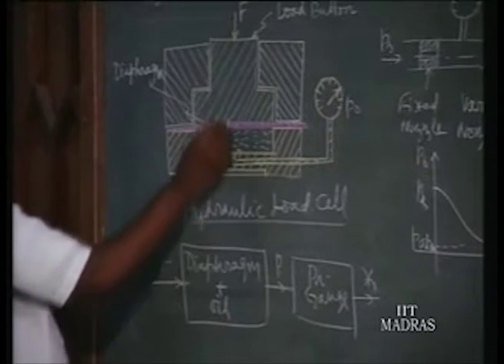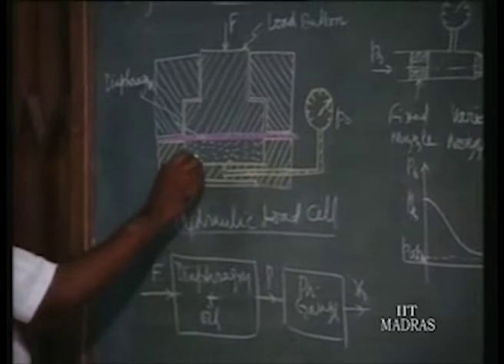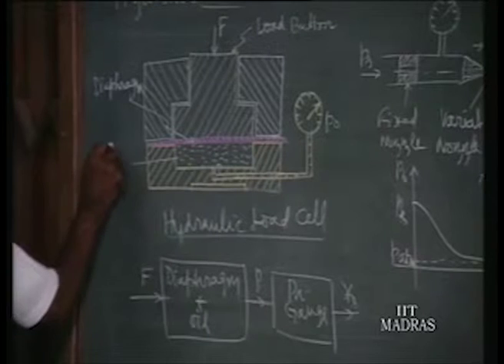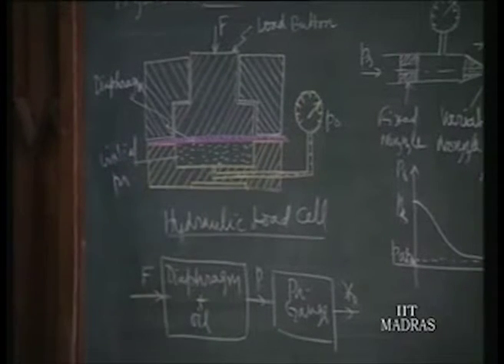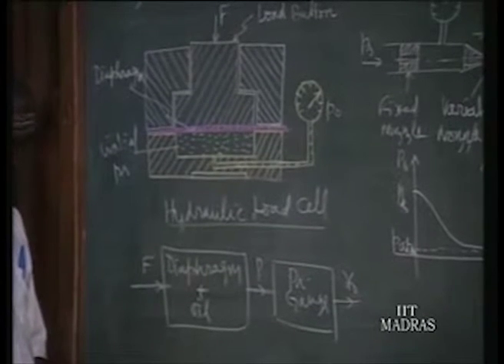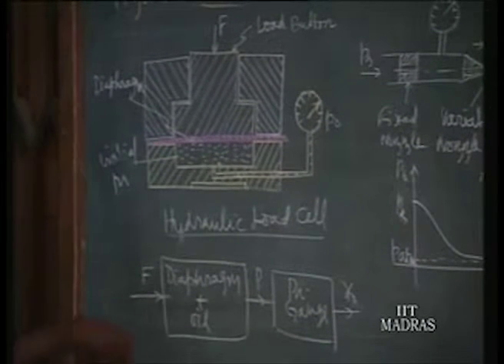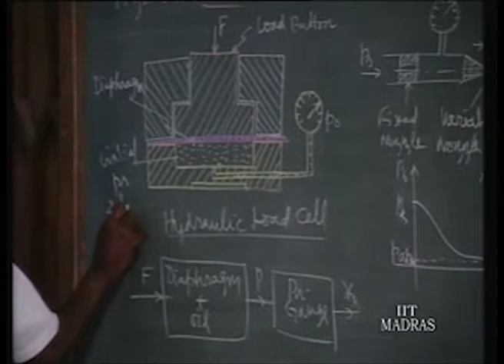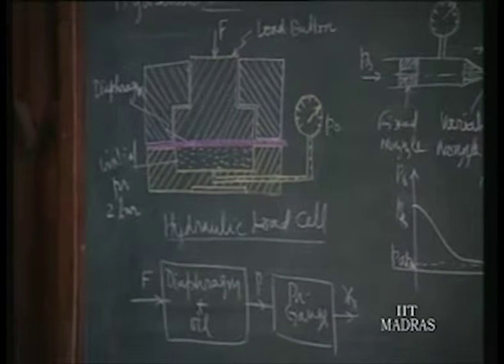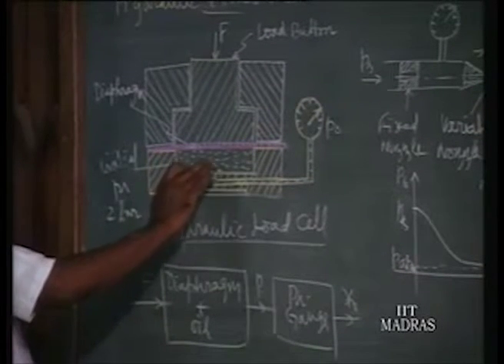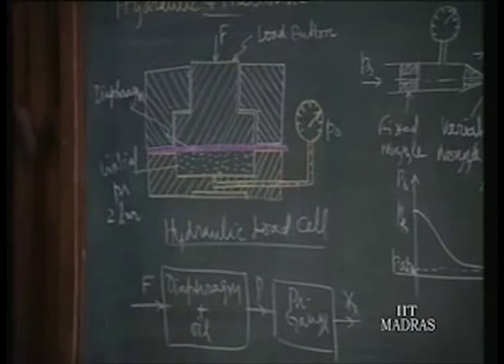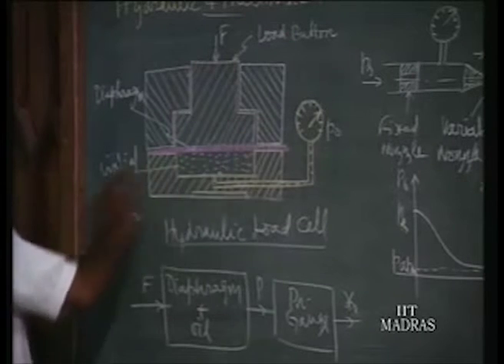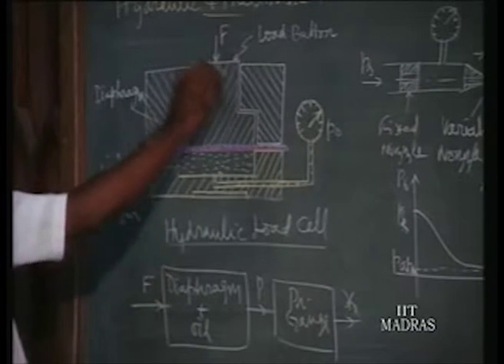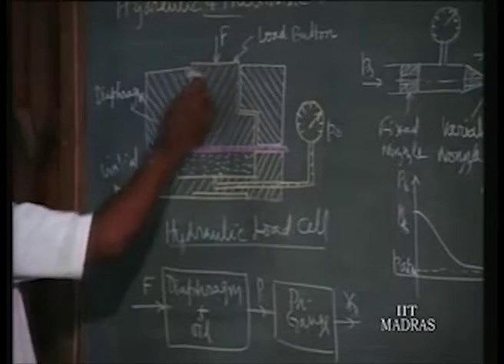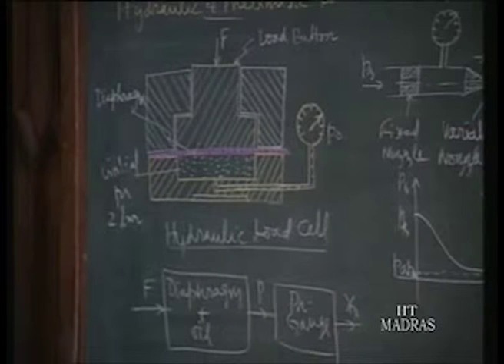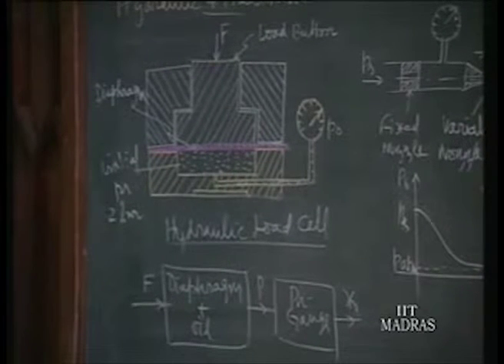So how do we ensure that the moment you apply a force, it is converted into pressure? That is achieved by having an initial pressure, of say 1 or 2 bar. It's of the order of 2 bar, that is 2 times atmosphere, or 0.2 Newton per millimeter square. A 2 bar pressure is built in. That is our initial pressure. So the pressure gauge may read 2 bar as the 0 input signal, so 0 force. Further increase can only come from the applied force. So that is a compact unit made up of hydraulic elements.